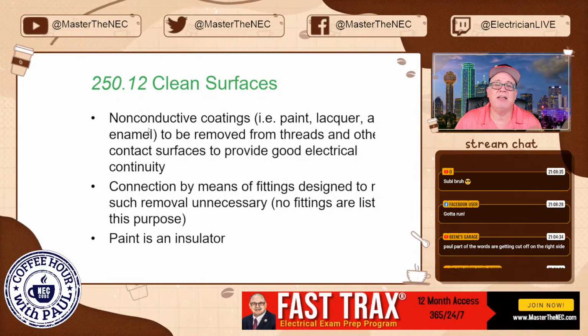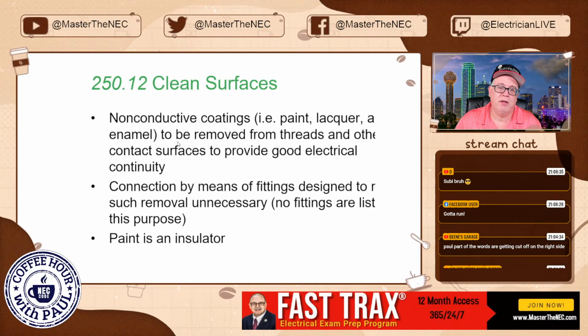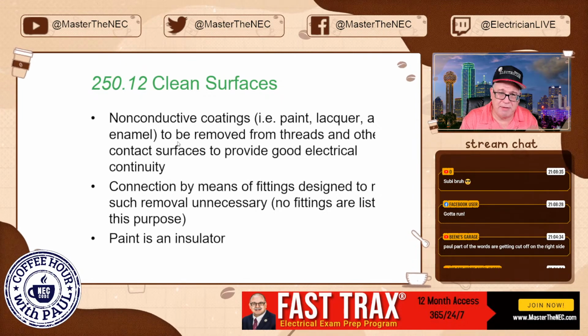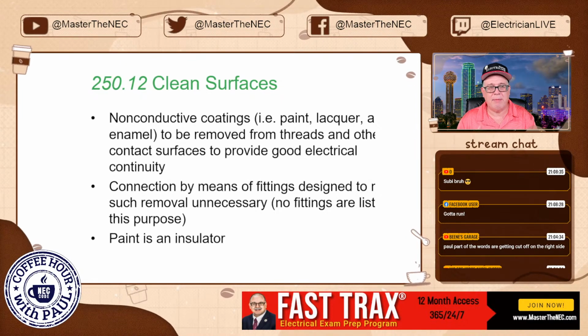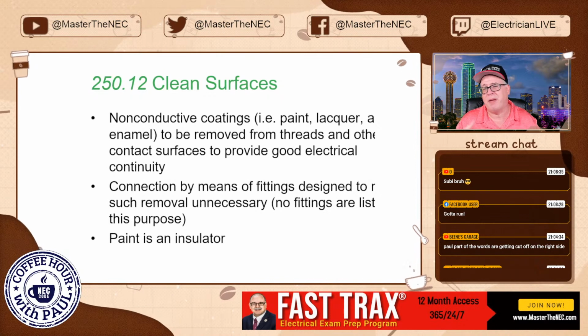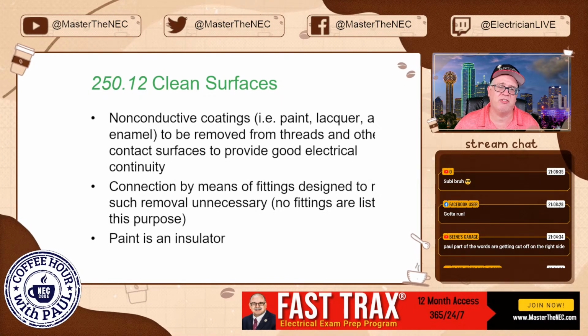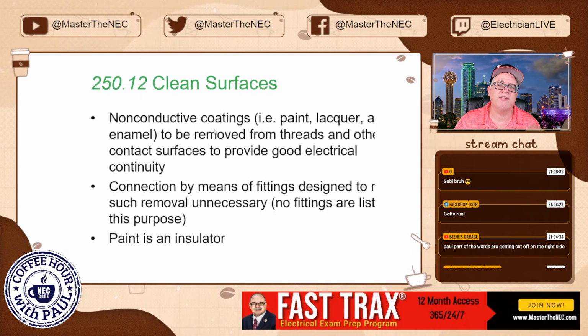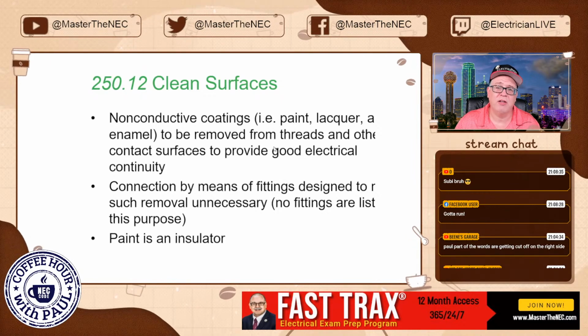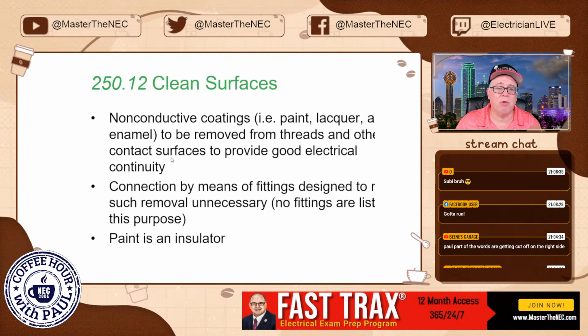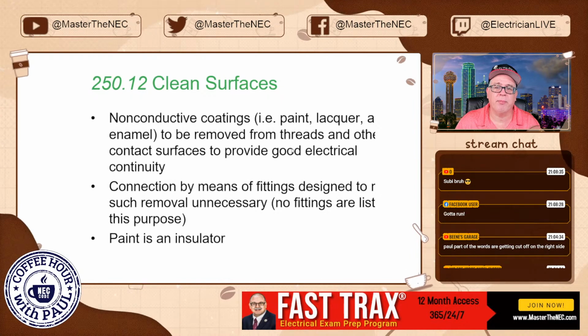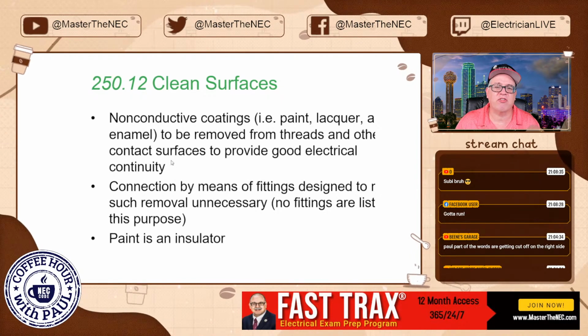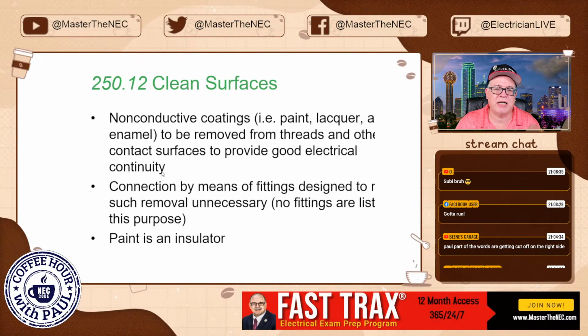All right, 250.12, clean surfaces. And this is when you're making connection to cabinets, enclosures, maybe it's baked on, or maybe it has paint on it or something like that. Here's what it says. Non-conductive coatings, such as paints, lacquers, and enamels, are to be removed from threads and other contact surfaces to provide good electrical continuity.